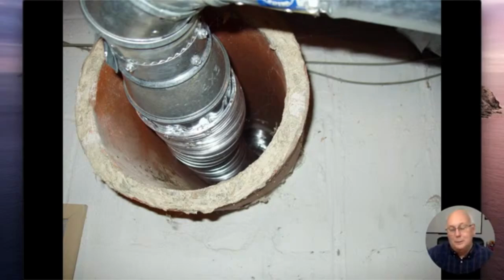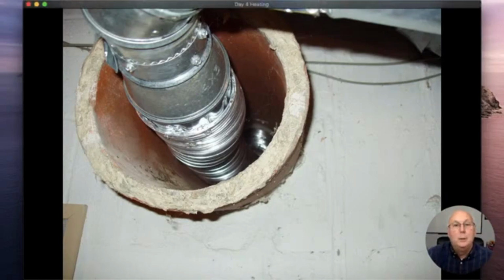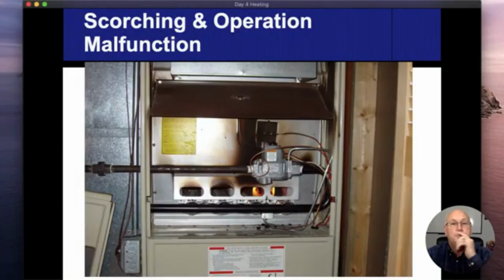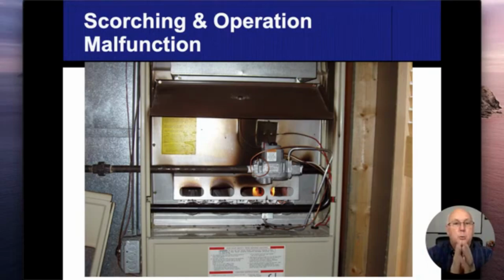But I do want you to know what a flue liner looks like, and again, it goes through and all the way up and out of the chimney. It's kind of a no-brainer. You see all that scorching in one spot. Look at the size of that pilot light on there too. But nonetheless, this was a definite hole in the heat exchanger, and every time that blower fan kicked on, it was pushing the air out of the burner chamber. In this case, it was actually backdrafting there.